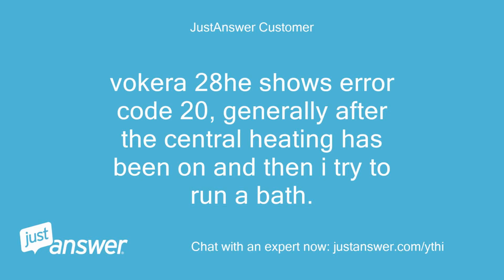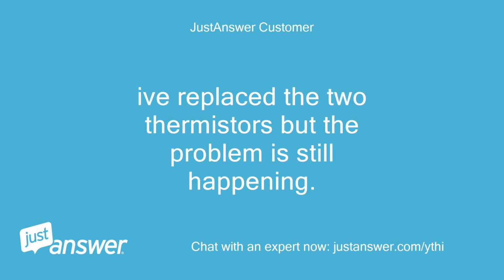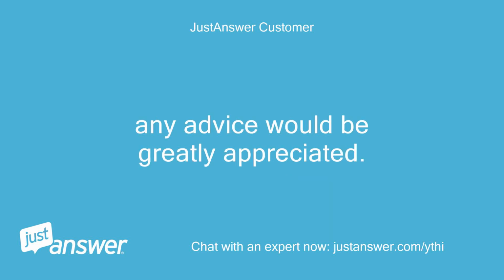Vokera 28HE shows error code 20, generally after the central heating has been on and then I try to run a bath. I reset the boiler, then it's hit or miss whether it goes into fault or not again. I've replaced the two thermistors, but the problem is still happening. Any advice would be greatly appreciated.